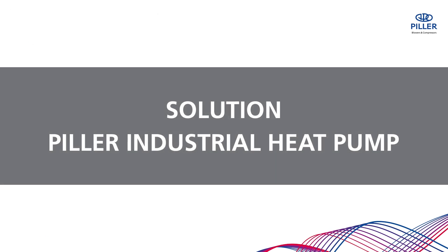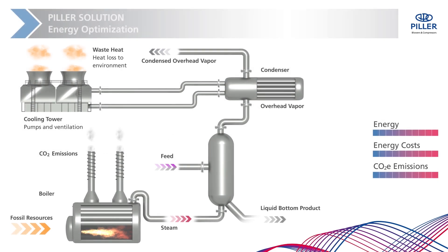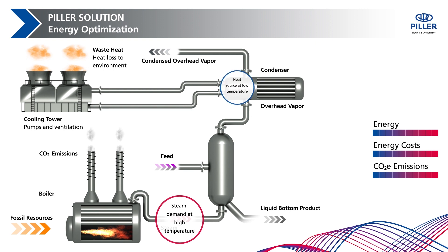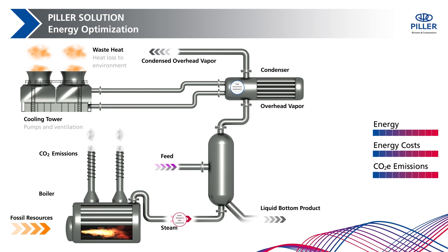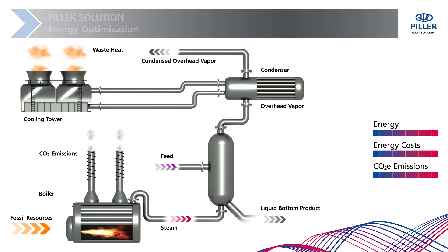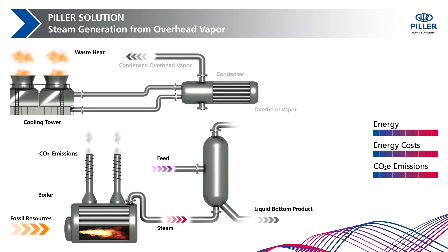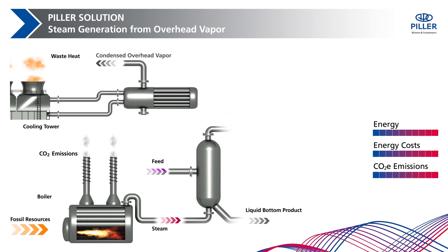Piller offers the solution for more energy efficiency and cost reduction. The energy supply is optimized by linking the steam demand with available waste heat sources. Due to the temperature difference between low-temperature waste heat and high-temperature steam demand, a heat pump is required. In this example, the Piller industrial heat pump recovers the waste heat from the separation process in an evaporator.